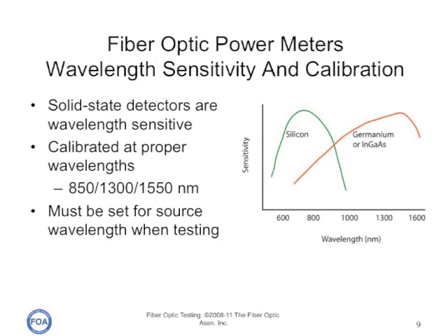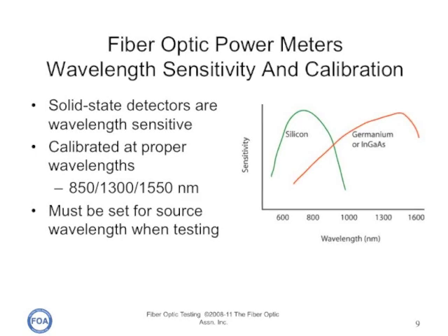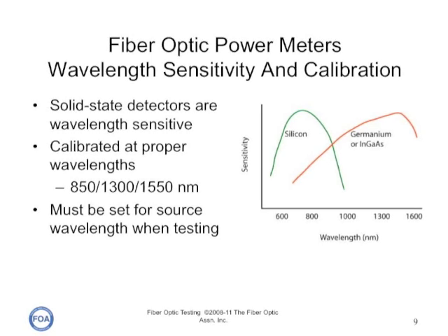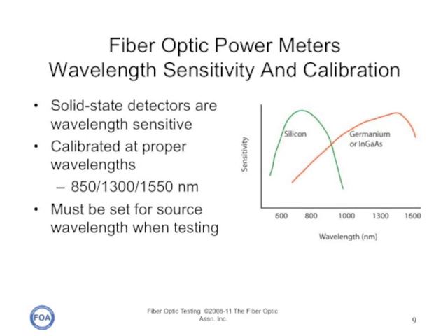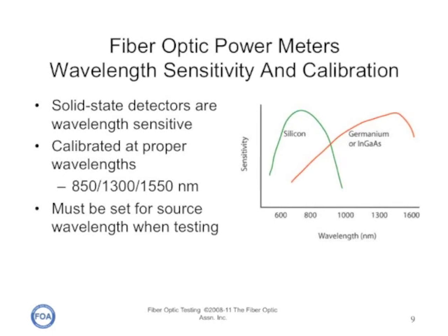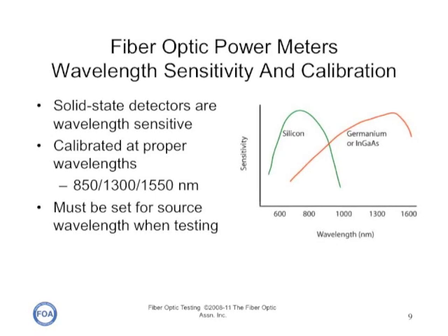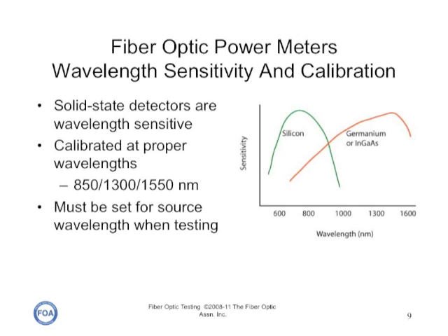Fiber optic power meters typically use solid state detectors that are wavelength sensitive. For short wavelengths, we use silicon detectors, and for long wavelengths, we use germanium or indium gallium arsenide. Because the sensitivity of the detectors depends on wavelength, we have to calibrate them carefully at 850, 1300, and 1550 nanometers. When measuring optical power, it's important to set the wavelength calibration of the fiber optic power meter to the wavelength of the source you're testing.